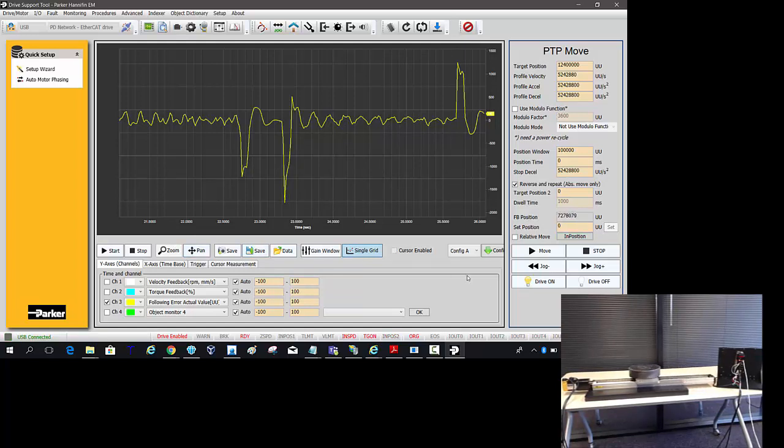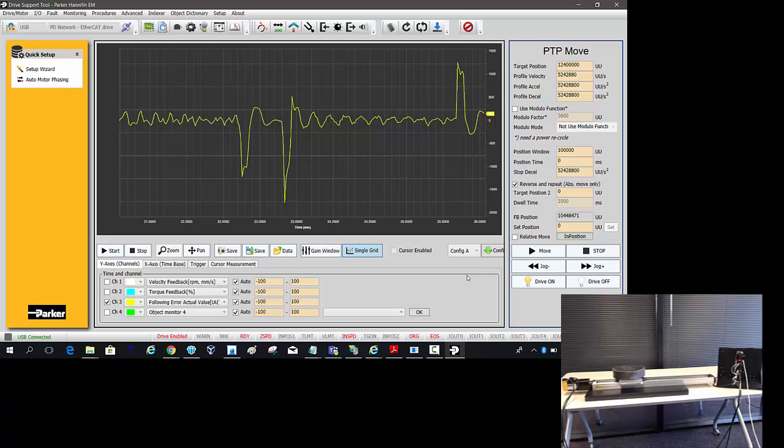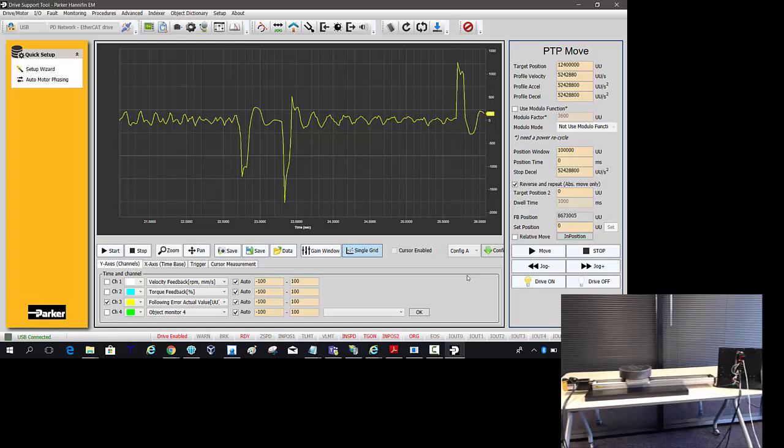So in summary, the default tuning gains will work nine times out of 10. If you want to dial it in, go into the gains, set the feed forward to 100%, then do the auto tuning, increase that up until you start to see a squeal, back it off a couple notches.